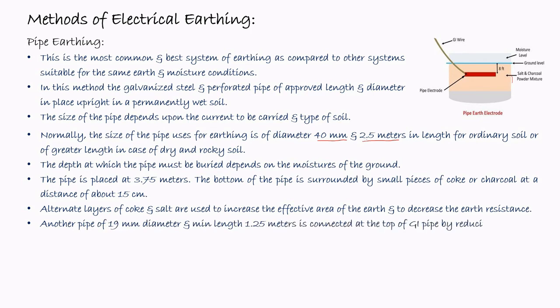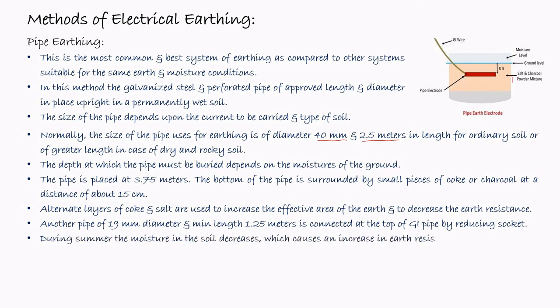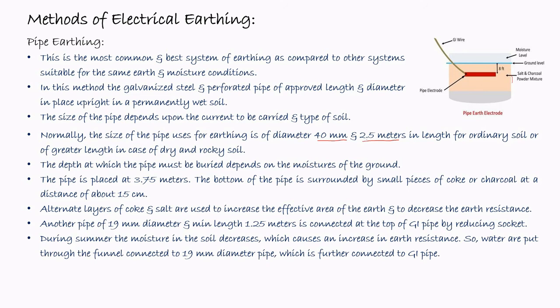Another pipe of 19 millimeter diameter and length of 1.25 meter is connected to the top of the GI pipe by a reducing socket. So here another pipe is connected with this GI pipe. During the summer, the moisture in the soil decreases, which causes an increase in the earth resistance. So water is poured through a funnel connected to the 19 millimeter pipe, which is further connected to the GI pipe. So in summer conditions, water can be put into the ground through this pipe, so that the soil stays moist and the resistance is minimum.